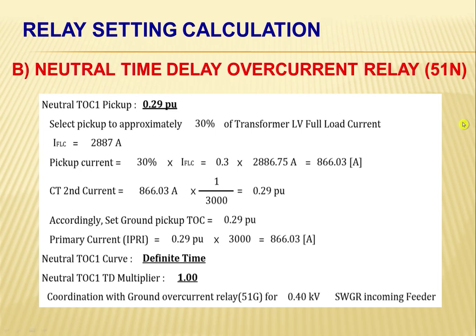For that, the pickup will be 30% of the transformer LV full load current. Our full load current is 2,887 when it is rounded off. So the pickup current will be 866 amperes. This will be multiplied by the ratio of our CT.